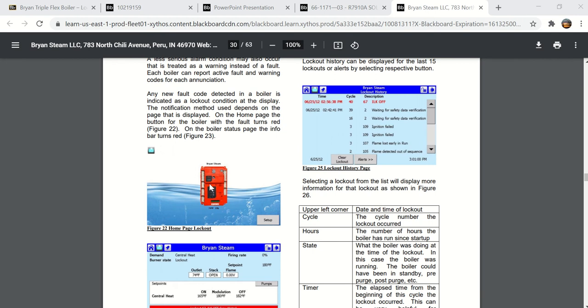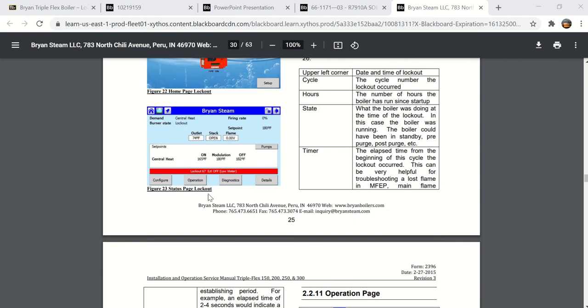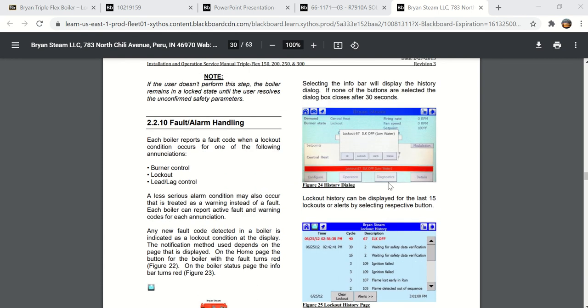Here, if you open up the main screen and you see this is in red, that means it's currently locked out. When you go to the main screen, you would see this history bar here, shows lockout 67, ILK off, low water. And you push that bar, and then this will pop up showing that it's off. If it's beeping, you can hit silence. If you want to reset it, you can hit, I think it's lockouts here, and it'll allow you to reset that.